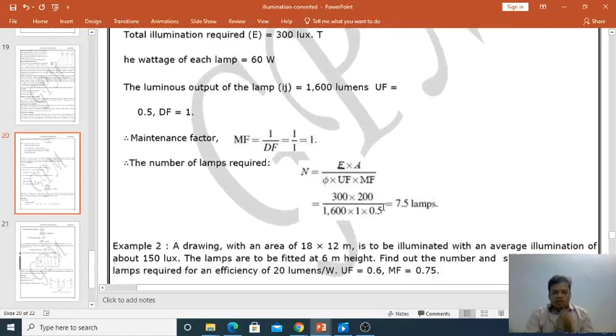For this, the solution: the area of the room A is 20 by 10 meters, that is equal to 200 square meters. Total illumination required E is equal to 300 lux, and the wattage of each lamp is 60 watts. The luminous output of the lamp is 1600 lumens, UF is equal to 0.5 and DF is equal to 1. Maintenance factor is equal to 1 by DF, that is 1 by 1, equal to 1. The number of lamps required is N equal to E into A by phi into UF into MF, that is 300 into 200 by 1600 into 1 into 0.5, that is 7.5 lamps.